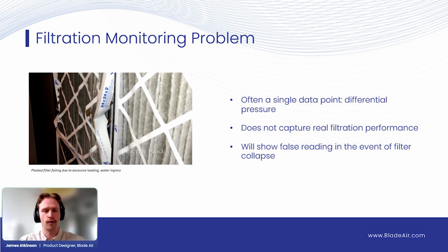All that dust is getting into your coils, your fans, your dampers, but you're not going to see that because there's no capture of that information. And this is a huge problem, especially for coils, right? The coils will foul. Basically, you'll have dust or biofilm accumulating on those energy transfer coils, and you'll get worse performance. So cooling is most heavily affected because it's a moist and damp environment. Heating, less so because the hot coils will self-disinfect a little bit. But it really shows that the industry, I think, for a long time, filtration was a checkbox, right? You had MERV 8, you have a filter, great, you're good to go.